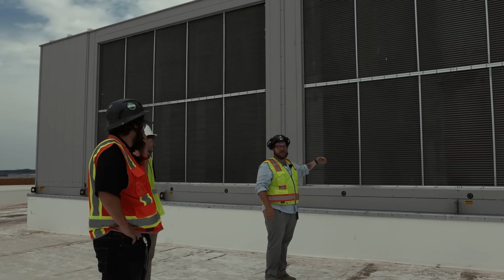These are going to be plumbed directly up to the HRMs. So they're acting like a thermal battery. The chiller plant up on the roof brings the temperature of the water down to within that bandwidth we have to hit for a target, and this is where it's storing it.